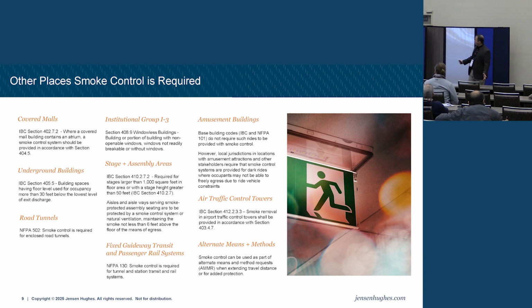Some other examples, and I won't read all of these. Covered malls, pretty common. Underground buildings, if it's 30 feet or more below grade and it's occupied. So does that mean a car park will have smoke control? Possibly, if there are occupied levels married to that parking in the lower levels, but there's also exhaust requirements for parking garages, so that you may have 2 different types of systems there.